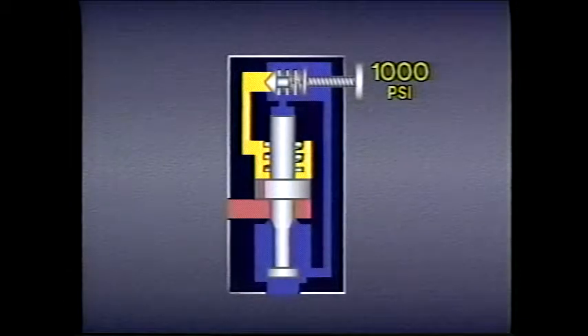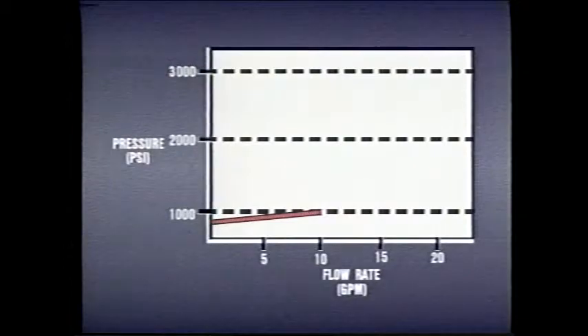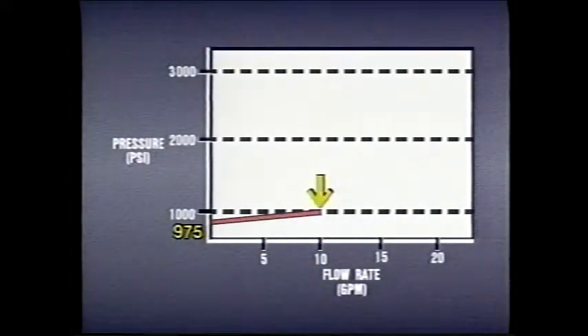Finally, when system pressure reaches 1,000 psi, the main valve spool opens. Since cracking of the main valve typically begins somewhere above 975 psi, the valve changes from completely closed to fully open with very little pressure differential. If we plot the performance on a graph, it closely follows the dotted line indicating the ideal condition — no flow at all is passed until 975 psi, and at 1,000 psi, with very little rise in pressure, the valve allows full flow.